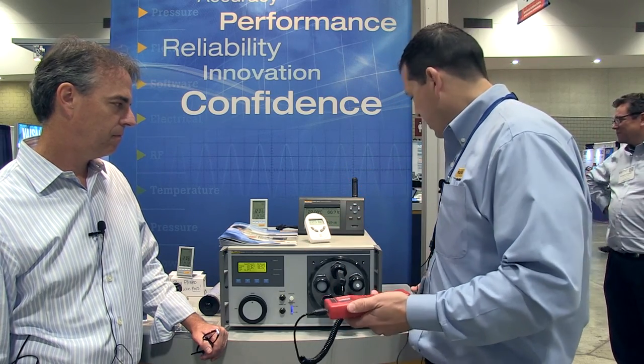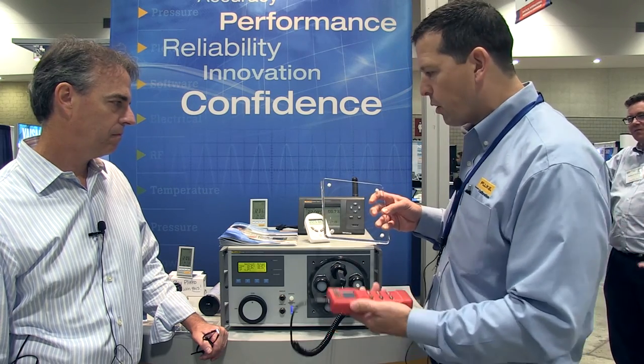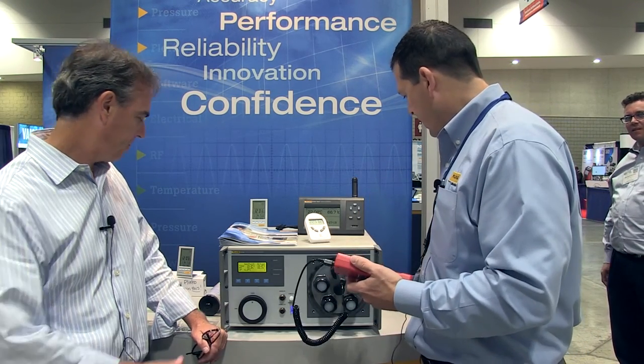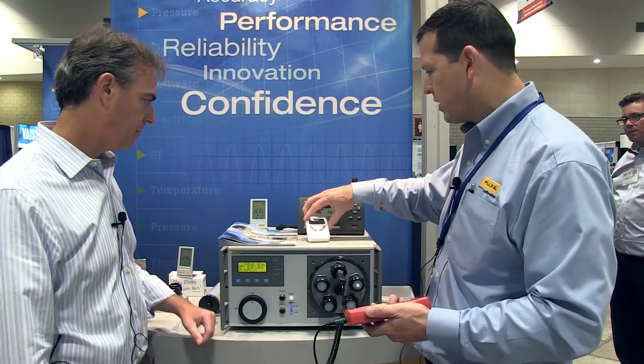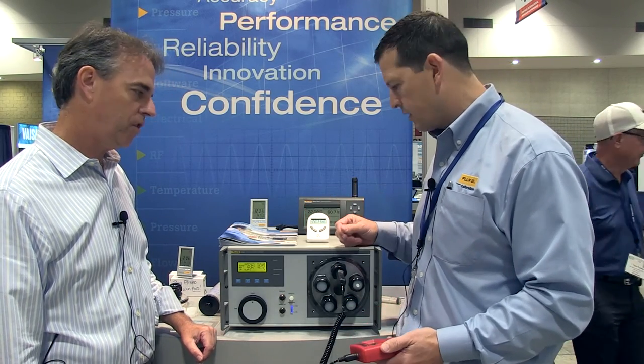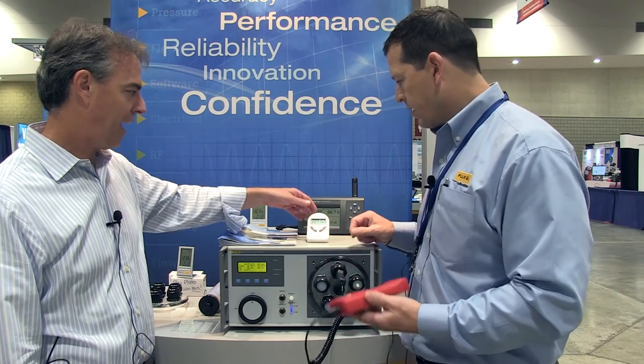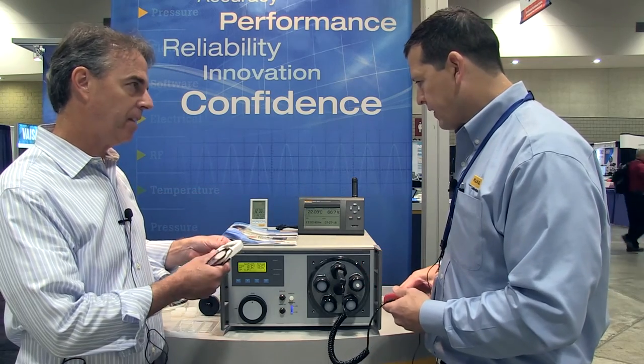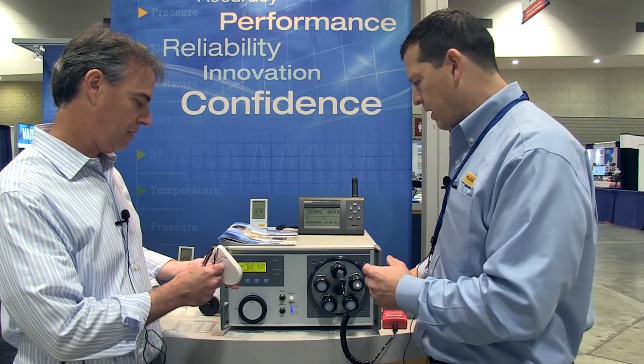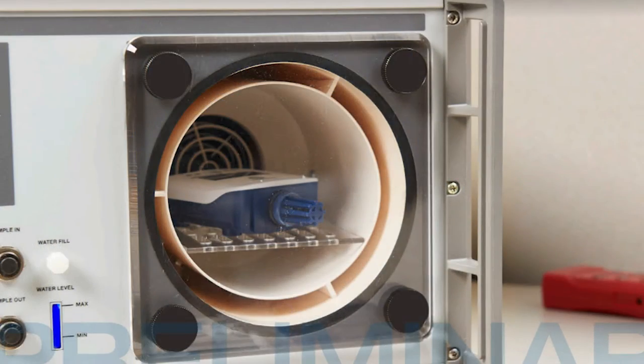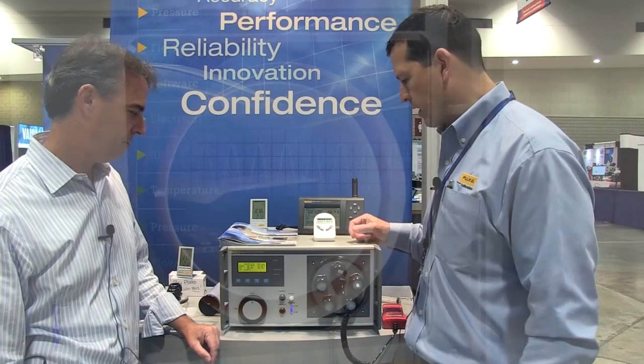Or as an alternative, you can take an accessory clear door that we have, which comes with a shelf that can be set inside the chamber so you can take loggers like these and put them directly inside - stack several of them at a time, as many as you can fit. You've got a little over about a 1 liter volume inside, so you could probably fit a couple of these at a time, depending on the size of what you have.